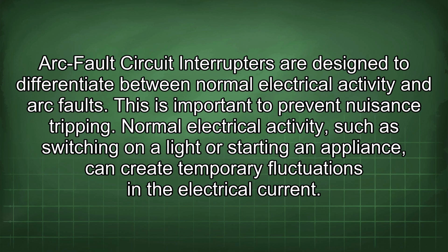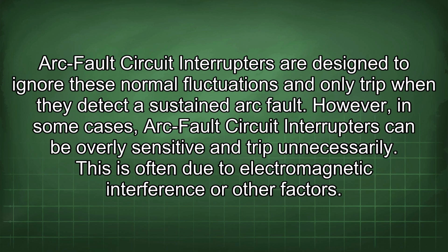Normal electrical activity, such as switching on a light or starting an appliance, can create temporary fluctuations in the electrical current. Arc fault circuit interrupters are designed to ignore these normal fluctuations and only trip when they detect a sustained arc fault. However, in some cases, arc fault circuit interrupters can be overly sensitive and trip unnecessarily. This is often due to electromagnetic interference or other factors.